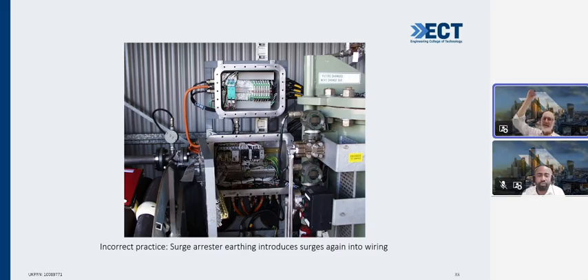So you'll get a surge coming through to the surge arrestor, but unfortunately the surge will be induced into the other cables as well. One has to be really, really vigilant about how one wires this up - it's reintroducing surges into the wiring. Very important to audit these processes afterwards.